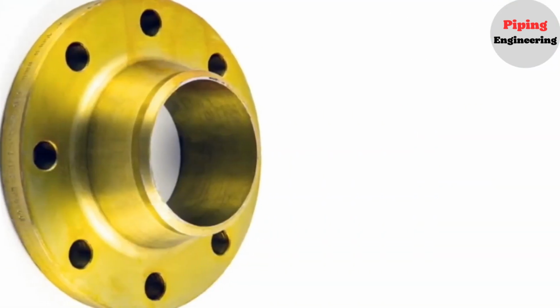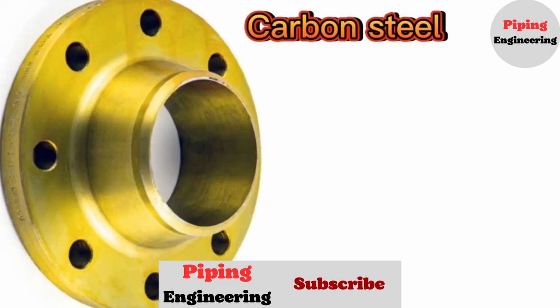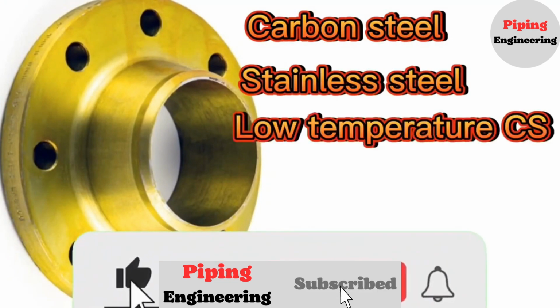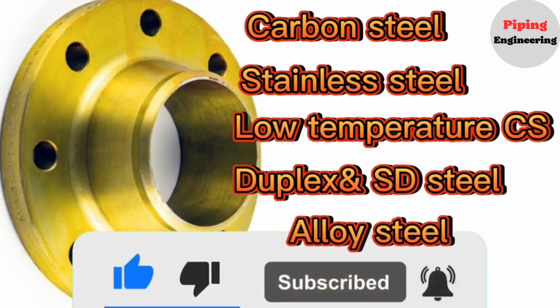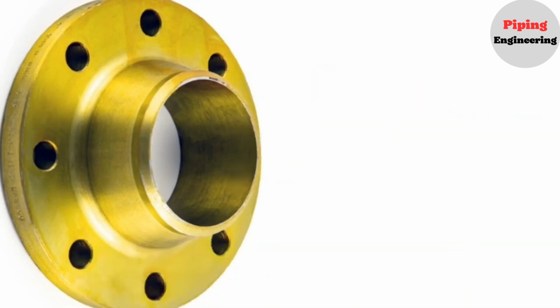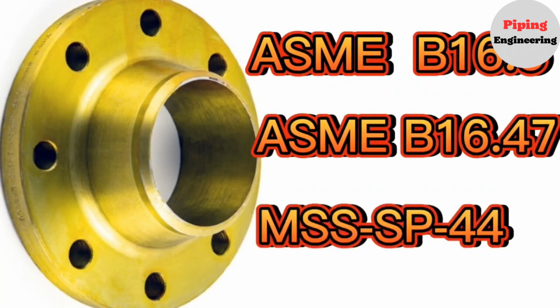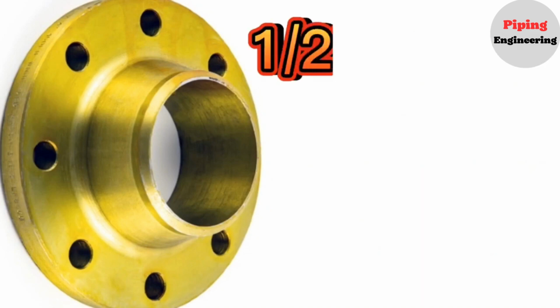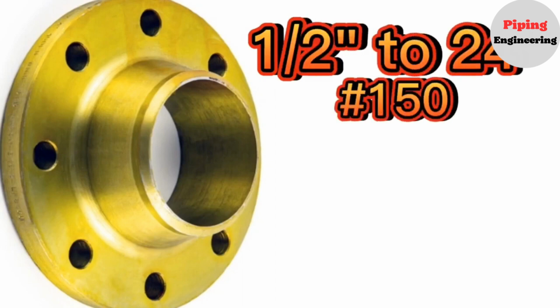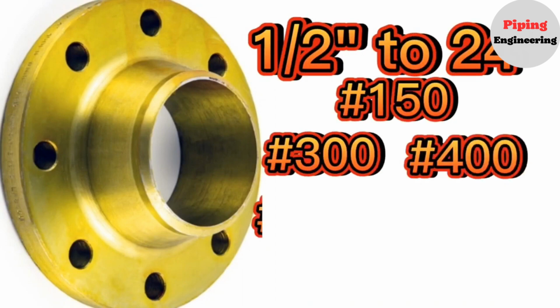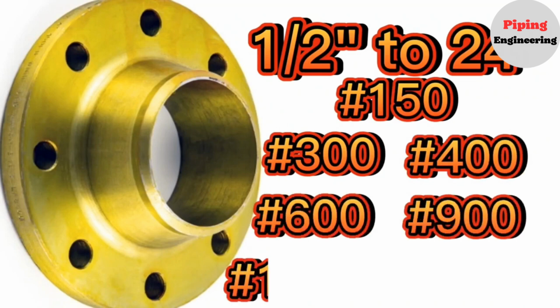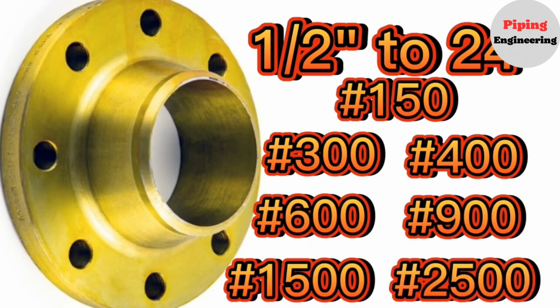Weld neck flanges are made from various materials like carbon steel, stainless steel, low-temperature carbon steel, duplex and super duplex steel, alloy steel, etc. Most commonly used dimensional standards for weld neck flanges are ASME B16.5, ASME B16.47, MSS SP-44. ASME B16.5 provides dimensions for weld neck flanges for size range 1/2 to 24 and for ratings 150, 300, 400, 600, 900, 1500 and 2500.